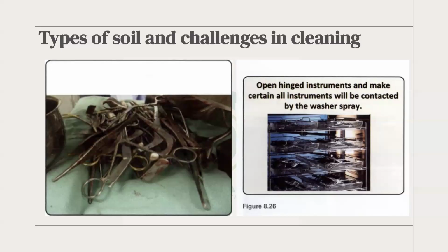And look at the other side. It's supposed to show you open hinge instruments. We have instruments that have to be open. Some you have to dismantle in a way so that the cylinder will be on the side and the base will be on the side so that it can wash properly. Okay? So open hinge instruments and make certain all instruments will be contacted by the washer spray. How you're putting them in there is like when we do grilling, right? Like summertime people do barbecue. See how they put their meat on the grill? Yes, so that every piece gets enough fire to cook it. That's what you should do. Every instrument that you put in there should be exposed to the spray. All right? The washer spray has to be able to spray every instrument in there. Are we all good with that? Yes. Okay, so let's go to the next slide.